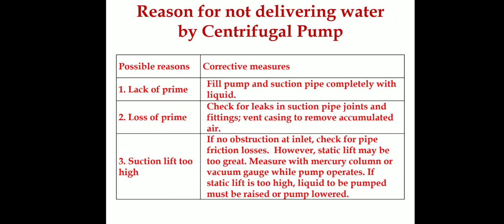In some conditions, the pump and motor are on but delivery is not happening. We will discuss the reasons. The first one is lack of priming. The suction pipe may not be filled with liquid.